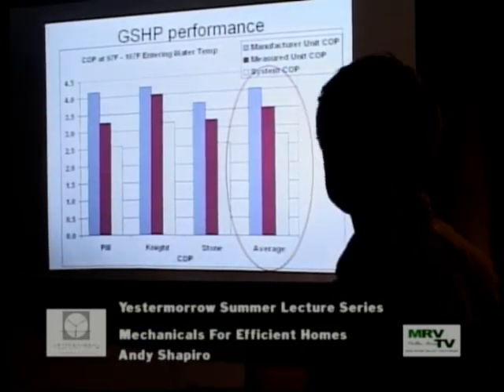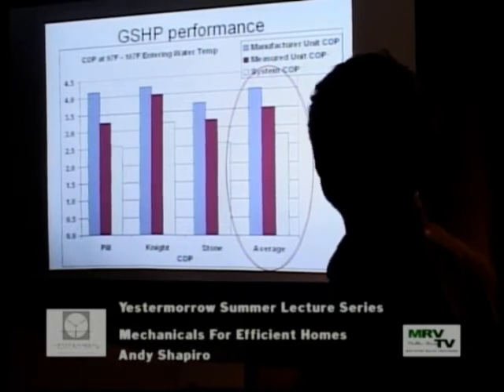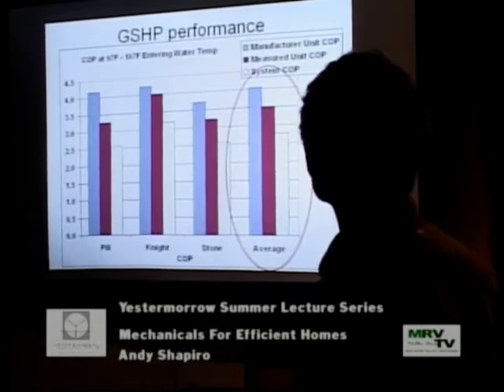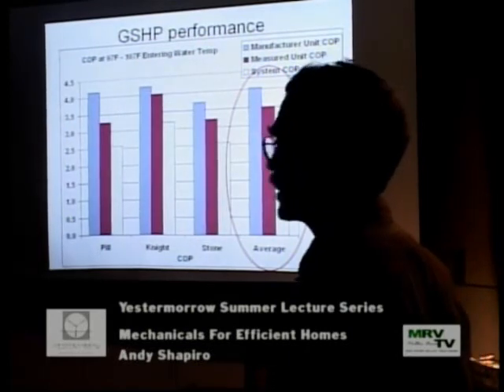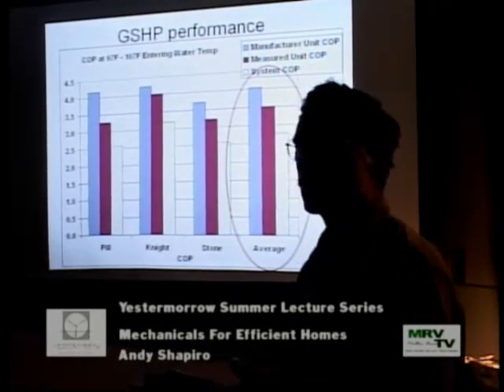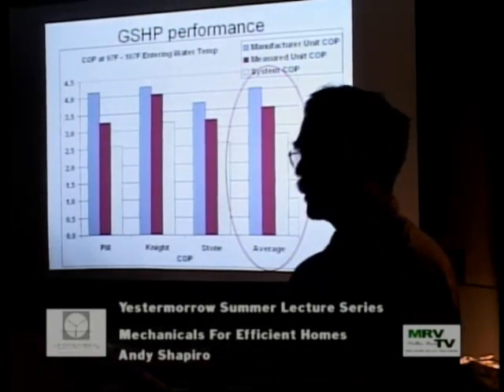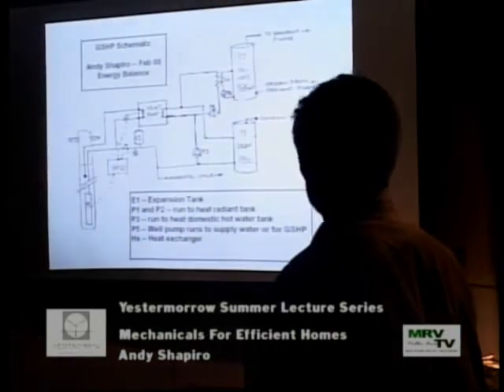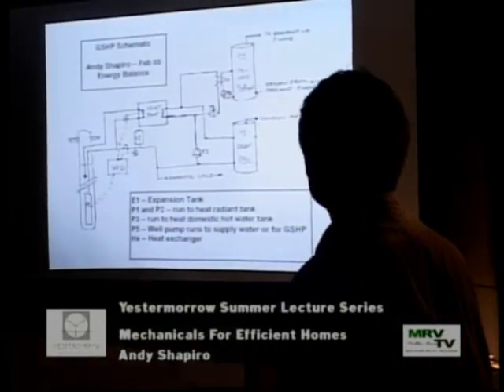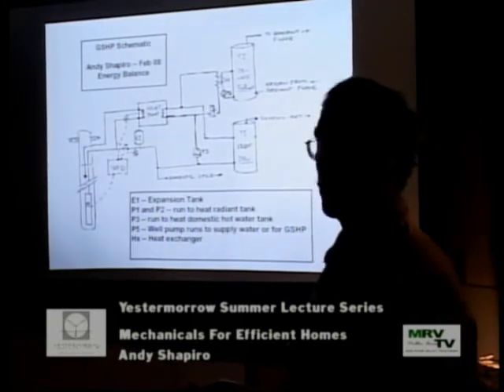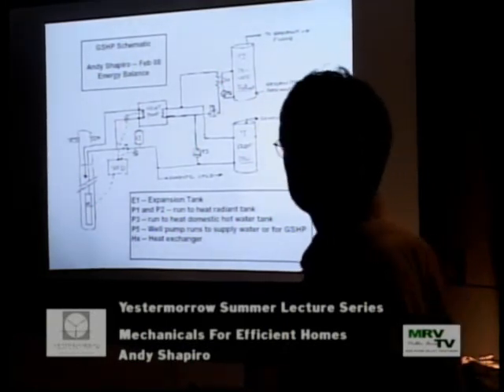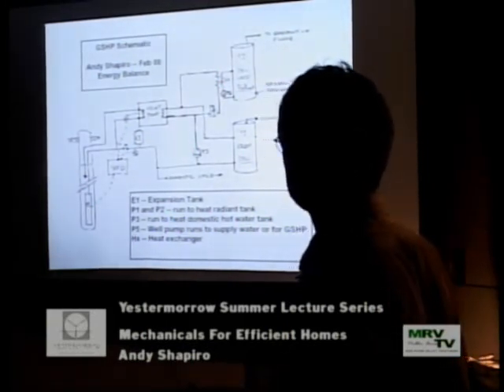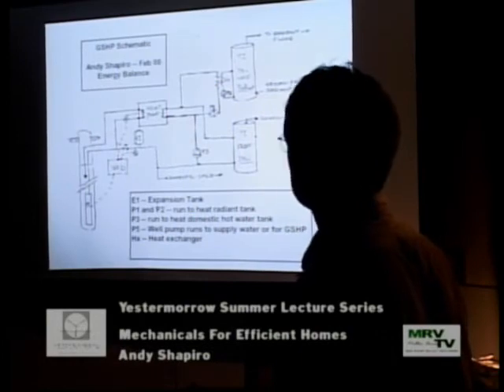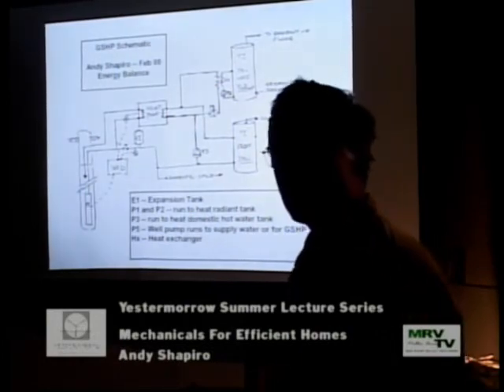This was some measurement I did on solar hot water systems, looking at this whole system coefficient of performance. So when you buy a heat pump, a ground source heat pump, they'll tell you what the coefficient of performance is of the box, right? Of this box right here. And it's usually quite good, like 5. I mean, it's a really great number, right? Well, but you've got to run the pump to bring the water in. You've got to run these pumps and they all take electricity.